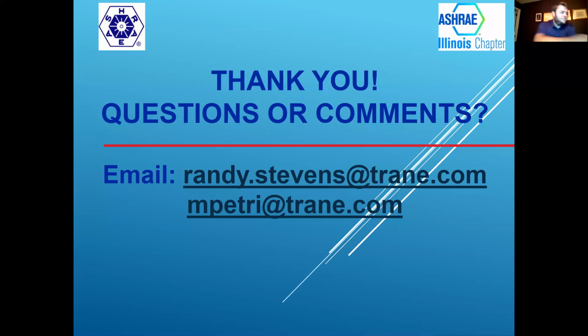Yeah, we have a question here. Is the 60% turn down limited to mainly VRF systems, or does it also apply to typical DX air handlers or rooftop units? That is strictly on VRF systems for this presentation. And then, Mike, what do you see on the turn down for split systems normally? Yeah, we wouldn't have that same limitation. I think they can certainly go down to 30 or 40% most likely.